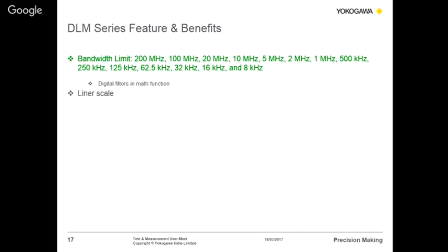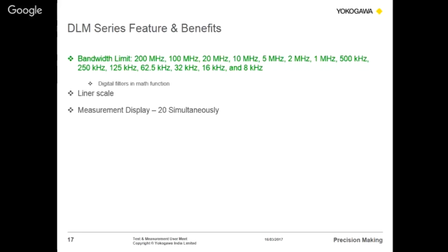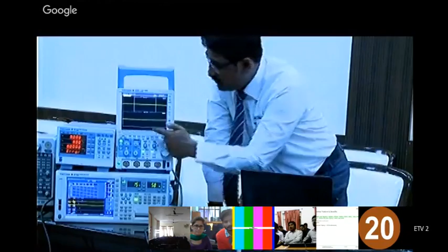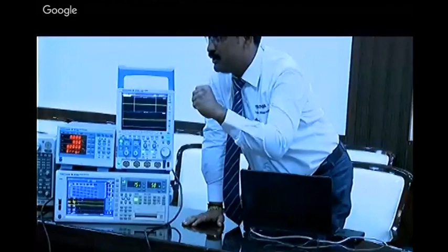And there's linear scale and measurement display of up to 20 measurements simultaneously. For example, if you see here on the screen, for any waveform you can display up to 20 numerical signals - you can calculate peak to peak or RMS voltage or frequency, and up to 20 such measurements can be seen simultaneously on the screen.